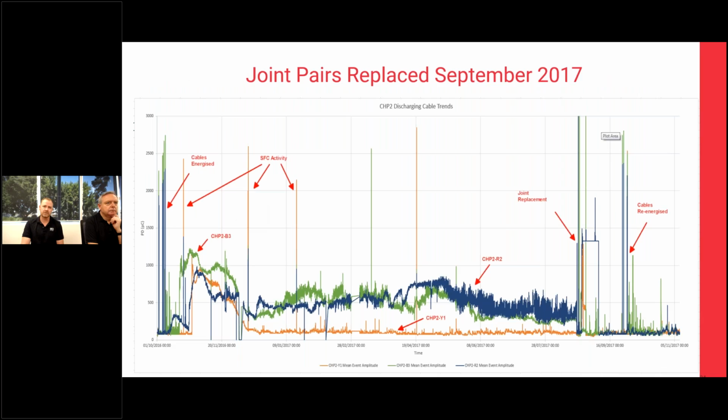They worked with us and the monitoring that we'd installed. We were able to remotely analyse the PD data and see how it was performing over time. They had planned a shutdown for 10 months into the future once they already knew there was PD on these cables. But we monitored them for the 10 months and reported to them about what was going on. So you can see in this trace that this green line here is the blue 3 cable.